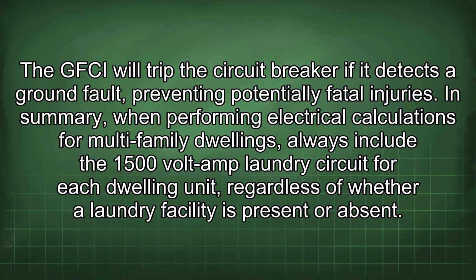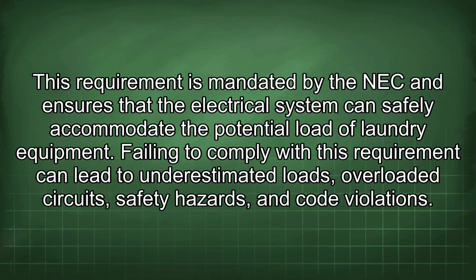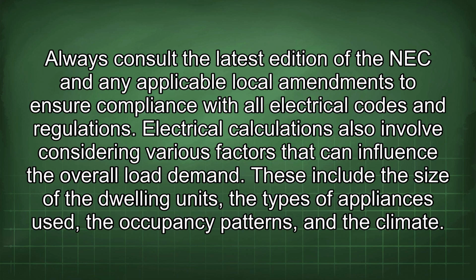In summary, when performing electrical calculations for multi-family dwellings, always include the 1500 volt amp laundry circuit for each dwelling unit, regardless of whether a laundry facility is present or absent. This requirement is mandated by the NEC and ensures that the electrical system can safely accommodate the potential load of laundry equipment. Failing to comply with this requirement can lead to underestimated loads, overloaded circuits, safety hazards, and code violations.